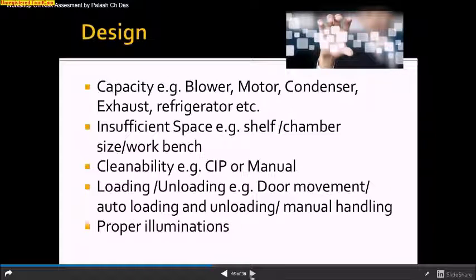So when you are talking about equipment, suppose you are going to procure some equipment, we have designed some components, sub-components. We need to give focus on those sub-components. First of all, it is design. When we are talking about the design, we need a URS for a machine. That is called user requirement specification. You need to clearly specify your user requirements, and your requirements are based on the risks. So it is recommended to make a risk assessment before you procure or plan for a machine. So this is the first criterion, that is design.